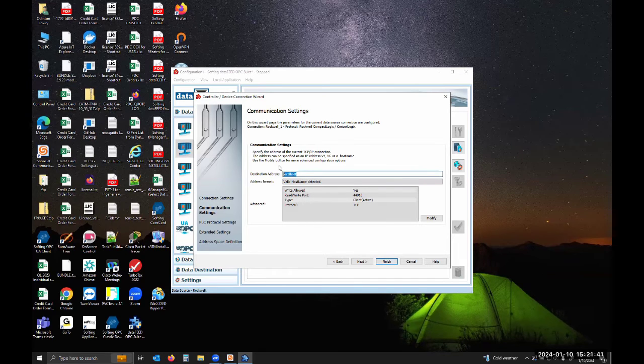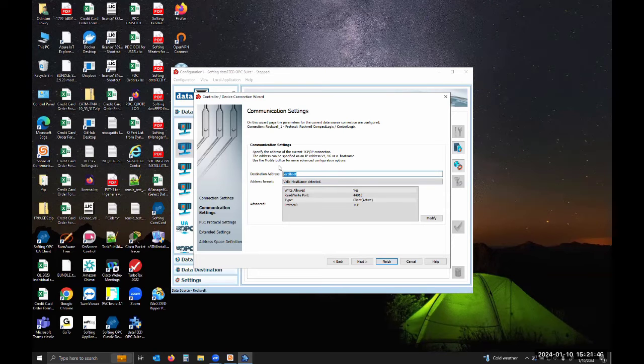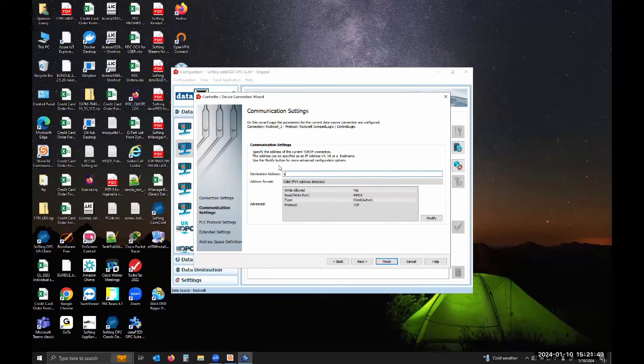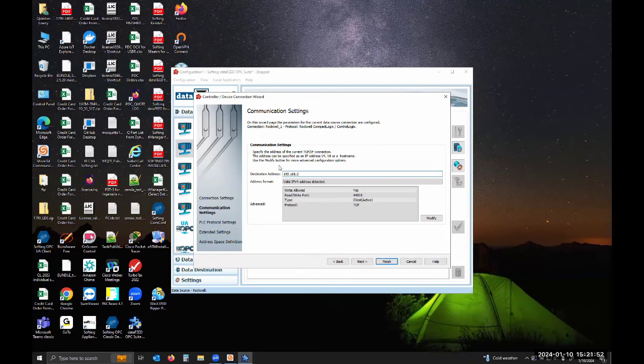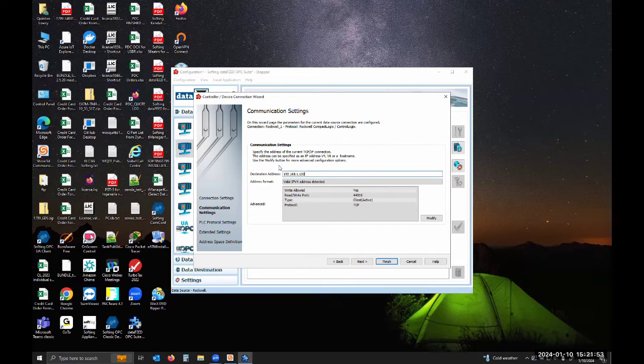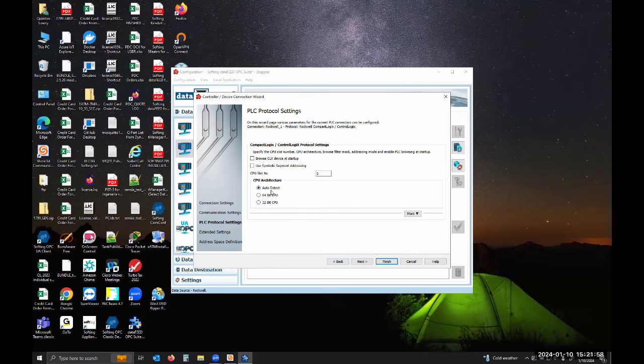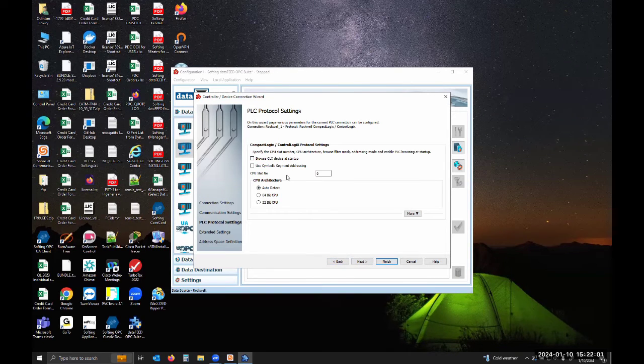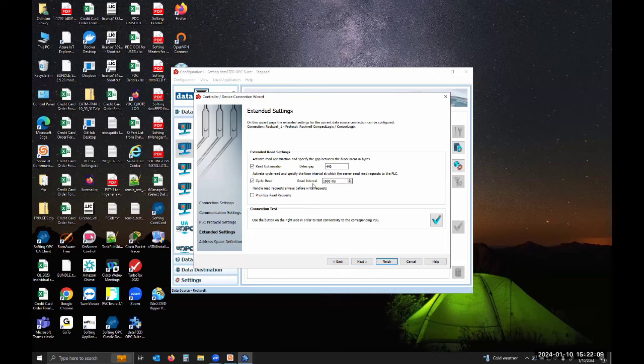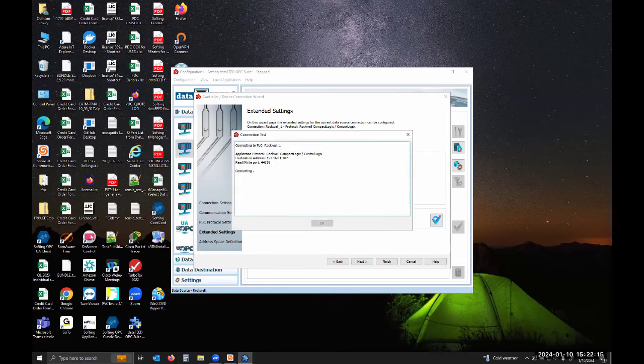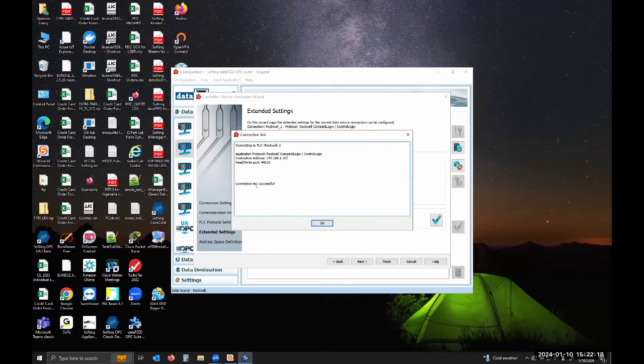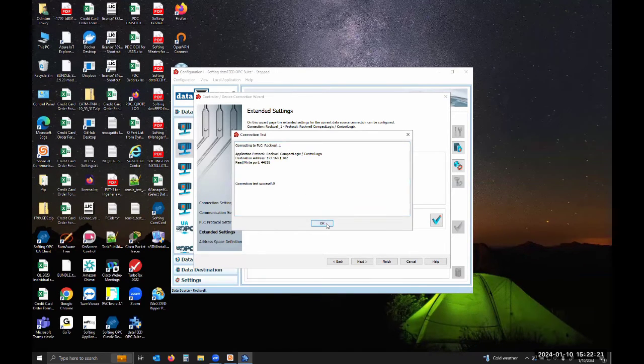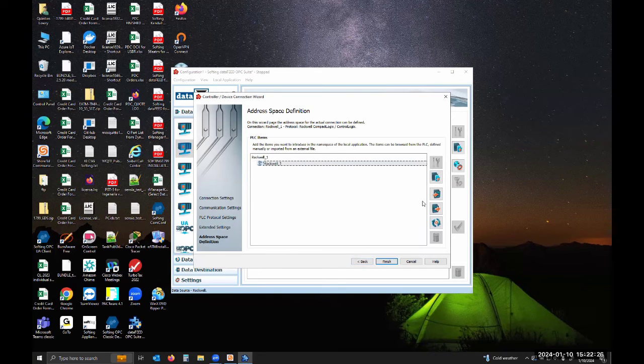In my case, I'm connecting to a Control Logix module, so I'm going to put in the IP address of my bridge card for that Control Logix module. I can hit next. You can hit browse CLX device at startup, so that's when data feed starts up. I'm going to leave it at the defaults. There's also other settings in here that you can modify, but I'm going to leave it as default. You can hit connection test and you can see we are successful. There is a controller at that IP address.